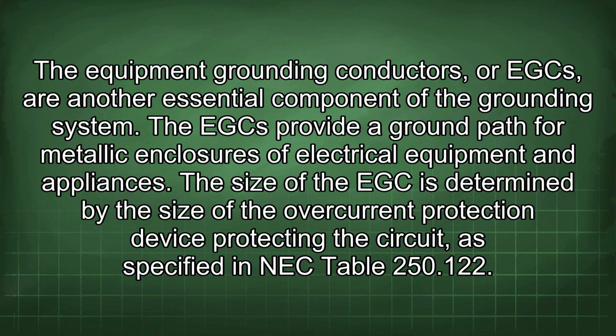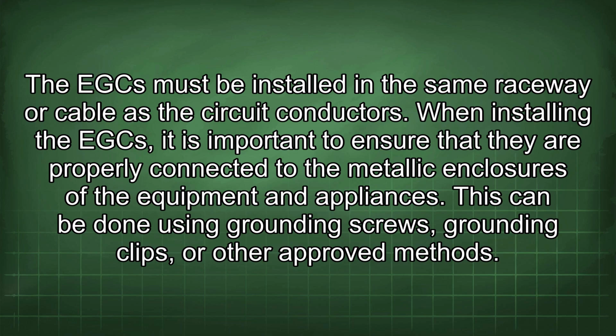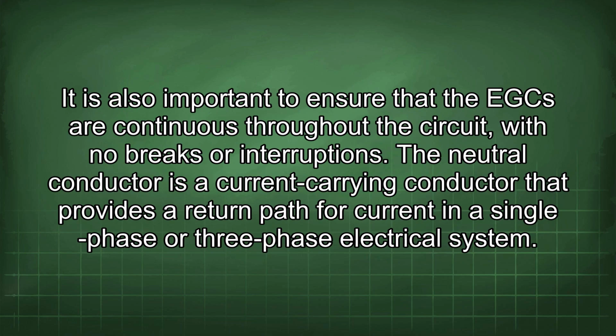The size of the EGC is determined by the size of the overcurrent protection device protecting the circuit, as specified in NEC Table 250.122. The EGC must be installed in the same raceway or cable as the circuit conductors. When installing the EGC, it is important to ensure that they are properly connected to the metallic enclosures of the equipment and appliances. This can be done using grounding screws, grounding clips, or other approved methods.